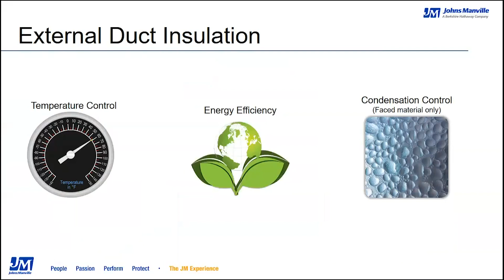One item of note here: if you're noticing I didn't mention anything about acoustics, duct wrap doesn't play a major role in controlling acoustics. Duct wrap is a wrap product that goes on the outside of a duct, so it doesn't provide a whole lot of acoustical benefit for your system. So when you're looking at specifications or a job and determining your insulation criteria, making sure you address or don't address acoustics with duct wrap is important to watch out for.